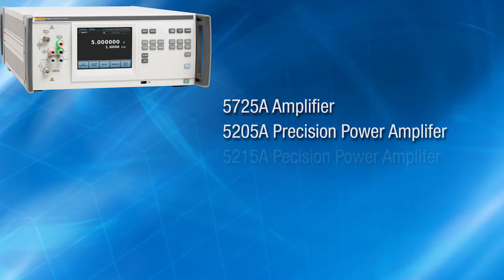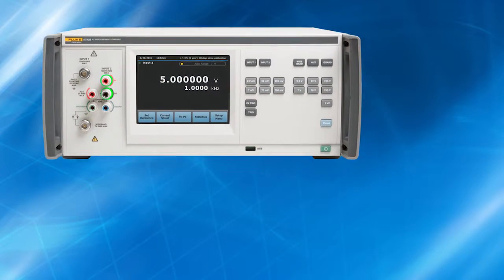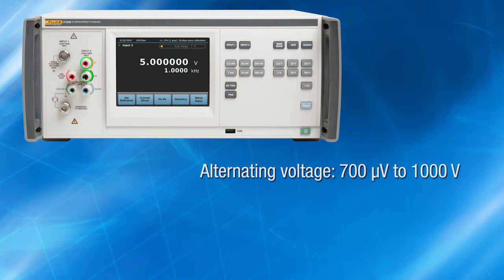The 5205A, the 5215A and transfer standards and AC voltmeters. The 5790B covers an alternating voltage range of 700 microvolts to 1000 volts and a frequency range of 10 hertz to 1 megahertz.